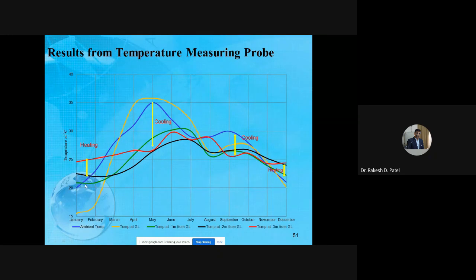The blue line shows the ambient air temperature throughout the year, and the red line shows the temperature at buried depth. The difference between the blue line and the red line shows the cooling as well as the heating effect from the buried tube exchangers. So in the month of May, the heat exchanger is used for cooling, and in December and January, I am using this heat exchanger for heating.